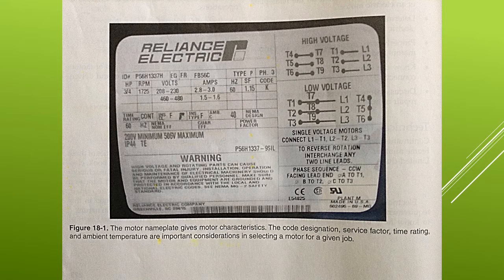The motor nameplates. One of the most important aids to installing and wiring a motor correctly is the information found on the motor itself, the nameplate, which provides a wealth of data regarding the characteristics of the motor.